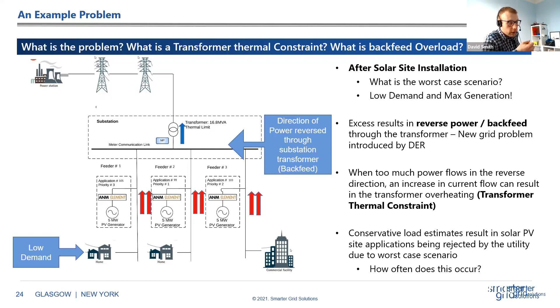So that is not ideal. And essentially what we do is provide software to let us dynamically control that distributed PV, so that when the constraint does happen, that one day a year, instead of paying however many million to reinforce the transformer, all we do is we turn down the PV. It sounds very simple, but it can be difficult in practice. And we'll talk through what that means.